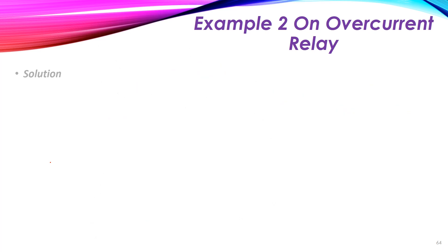How can we do this? First, we need to get the pickup current, the plug setting multiplier, and then from the table we will get the time. For relay number one, the fault current flowing inside the relay equals the actual fault current of 2000 amperes multiplied by the CT ratio of 1 over 200, so the current flowing inside the relay is 10 amperes.